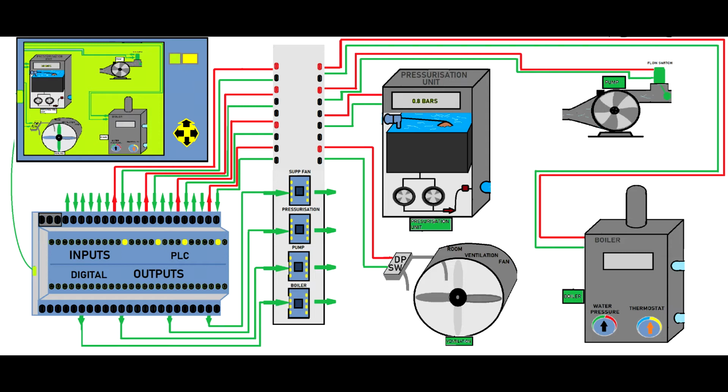It will give a little bit of time until the unit sets up, and then if the answer is not coming, the system might go on fault. So now we enable the supply fan which ventilates the boiler room. As you will see, the signal is not returning yet, but then the fan starts, and the differential pressure switch which is near the fan closes the circuit, sending the signal back to the PLC.